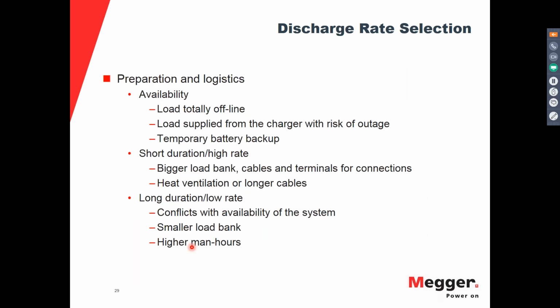Also, if you are getting prepared for the test, you need to consider the availability. If you don't have all the means, you might have the load totally offline, or you might have it depending just on the charger while the battery is being tested. But if something happens and you lose the charger and you don't have a backup, you have to consider a backup. So these are things that add a cost to the test, and also all of the preparation and the resources that you need to consider.